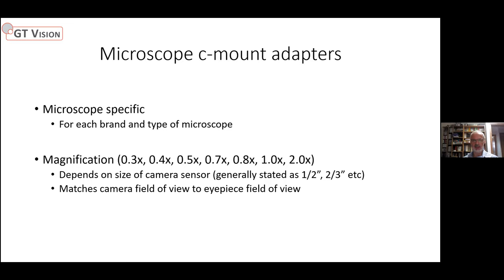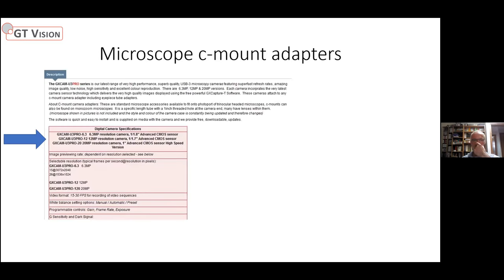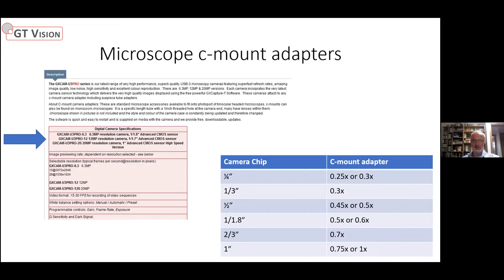You can use a higher magnification adapter to get bigger magnification, but generally matching the eyepiece to the camera display is a nice way to do it. Our website shows cameras like the U3 Pro 20, which has a one-inch sensor, and the U3 Pro 6.3, which has about a half-inch sensor. For a half-inch sensor you need around a 0.5x c-mount, and for a one-inch sensor you need a 0.75 or 1x c-mount adapter. Using these tables you can match the camera and adapter quite nicely.